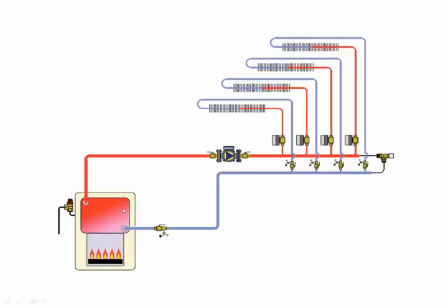So we want to get rid of this air. Knowing this property of air, let's take a very basic hydronic system. Let's say it's a heating system. We have a high mass boiler here, a pump, and some zone valves, and let's say it's all on one level. Where would we put our automatic air separator?